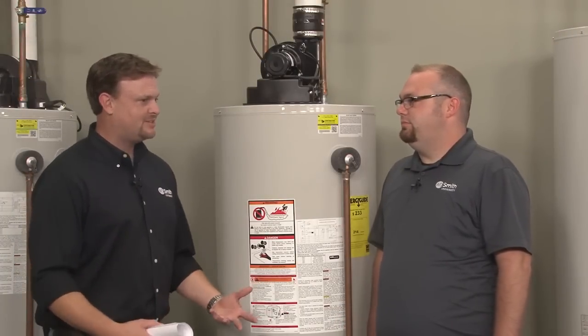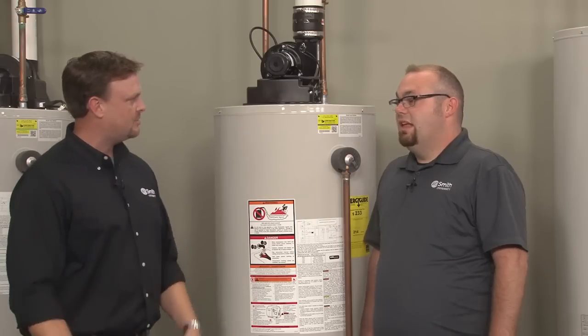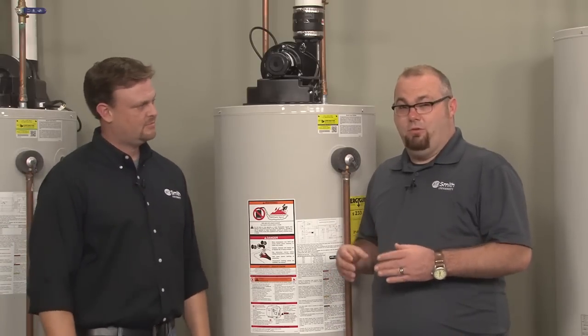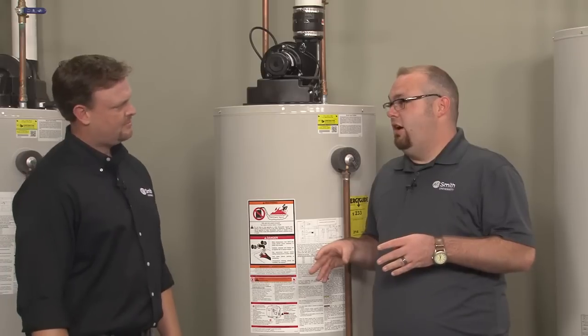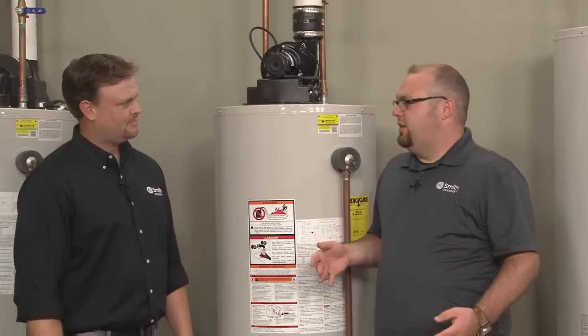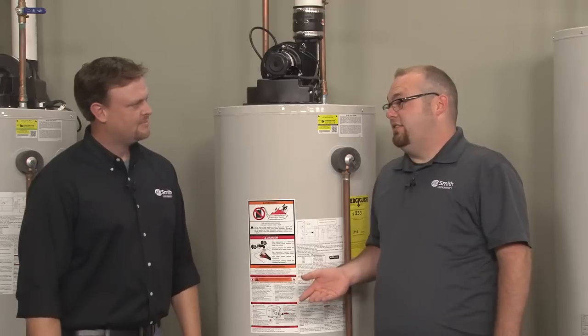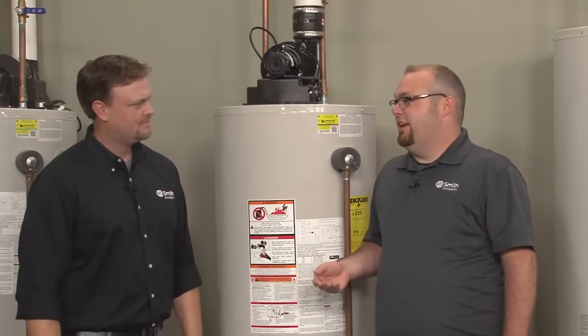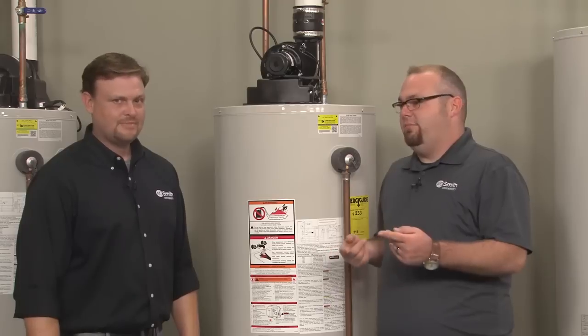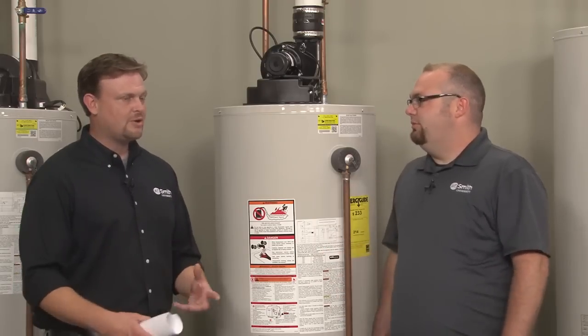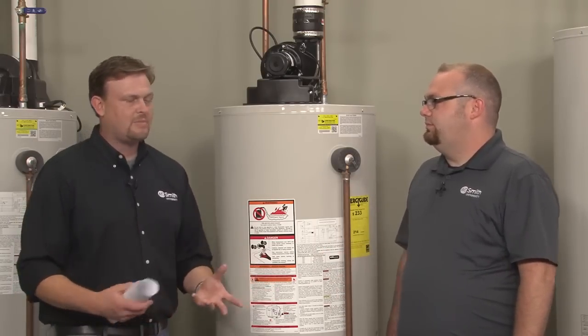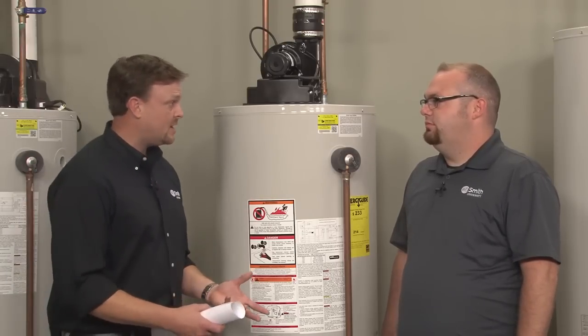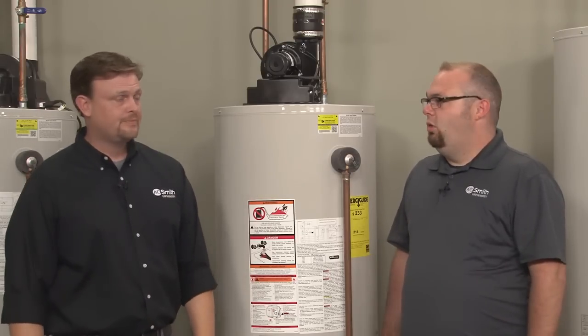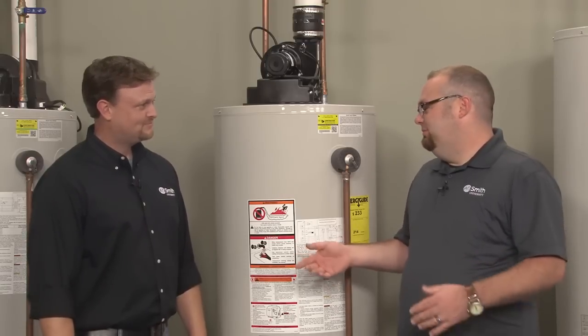All right, what if it does light, but then it goes immediately out? If you get a burner flame for around 4 seconds and it just turns automatically back off, usually it's going to be something electrical. In this case, it's going to be flame sense. Typically, a dirty flame sensor is not able to conduct that signal. Okay, so I'm going to go ahead and clean that. What am I going to use? I'll probably use some fine grade steel wool. Just polish up the rod. Make sure when it does ignite that the rod's burning in the flame. It should be, but that's usually it.